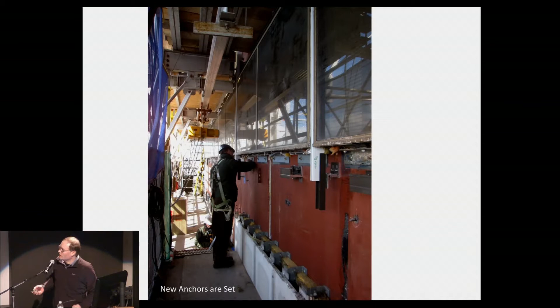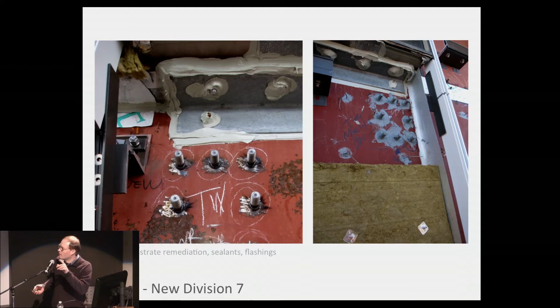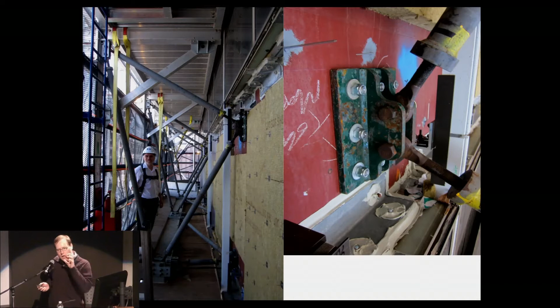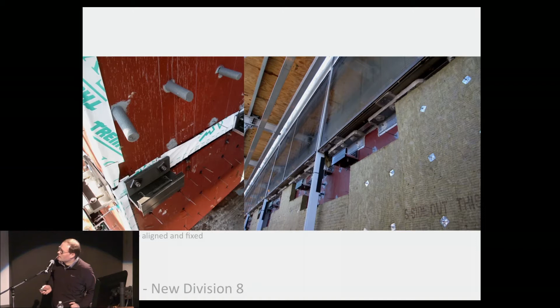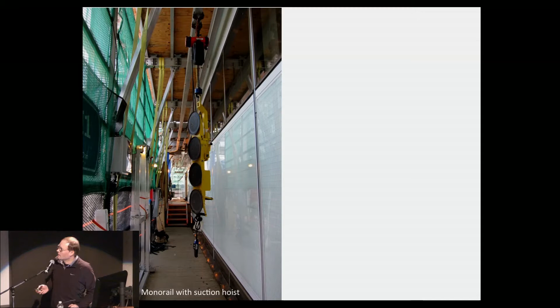Cleaning up the insulation, putting on new anchors, putting on new insulation. This is fire-rated insulation, 5 inches of mineral wool. These are the studs that are welded on that will carry the custom anchors that lock the system in place and make it quite unique and very, very durable. There's the new anchors. We're taping it. If there are any cracks or holes, we're replacing that. And here's the new glass, and this is how it was installed.